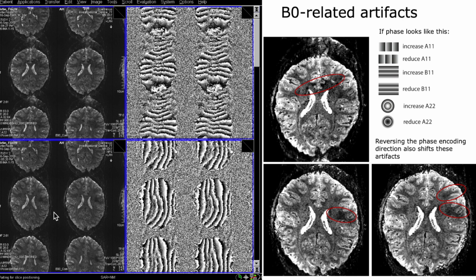So in the case down there, I, for example, did not manipulate the B11, but the A11 shim current. And then you see that the frontal part is now kind of resolved. I don't have these black spots anymore, but I have a new spot right over there.